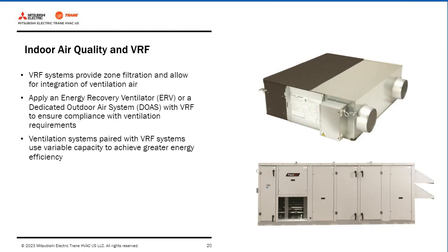So ventilation, that's the first question we get asked on VRF all the time. And proper ventilation is a huge priority. Coupled with VRF zoning technology, airflow is never recirculated from one zone to another. This method of operation enhances indoor air quality. By using ERVs to recover the waste energy from a building by capturing and repurposing thermal energy from exhaust air, you can move the building's exhaust air through a heat exchanger where it meets and tempers a stream of outside ventilation air that the ERV moves into the building from another direction. Through this crossing of streams at the heat exchanger, the ERV recovers about 70% of sensible energy and 60% of latent energy. ERVs are cost-effective in moderate or dry climates.